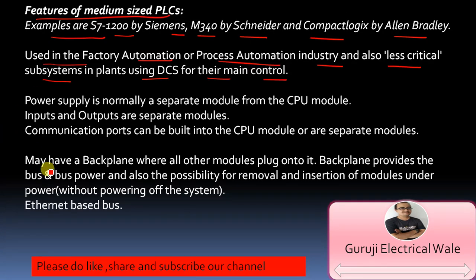then we see here we may have a backplane where all other modules plug onto it. Backplane provides the bus and bus power, and also the possibility for removal and insertion of modules under power without powering off the system. Backplane means if you want to extend, let's say if you want to extend the input output modules, you have that facility.